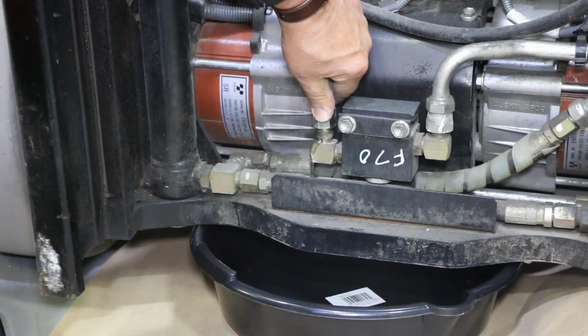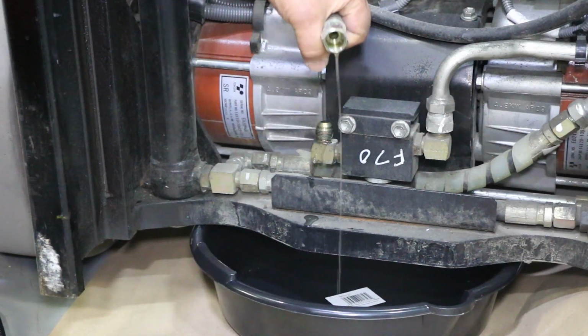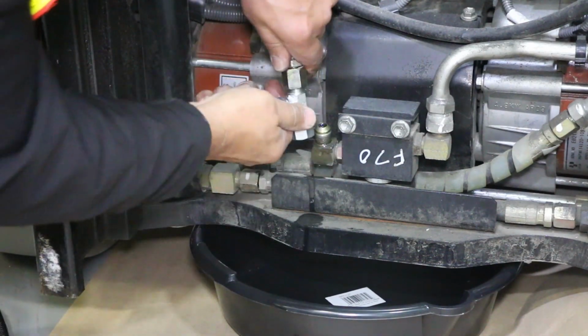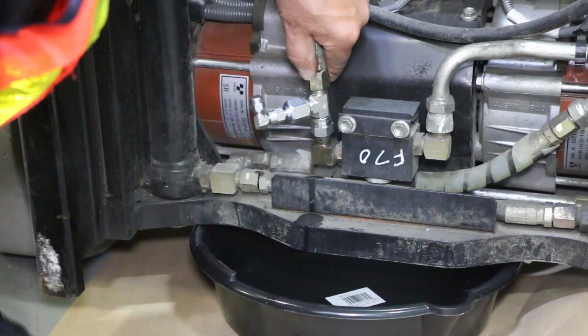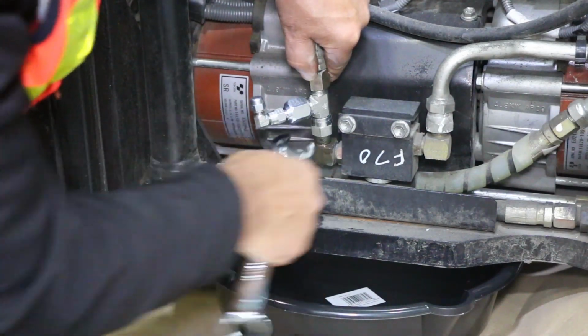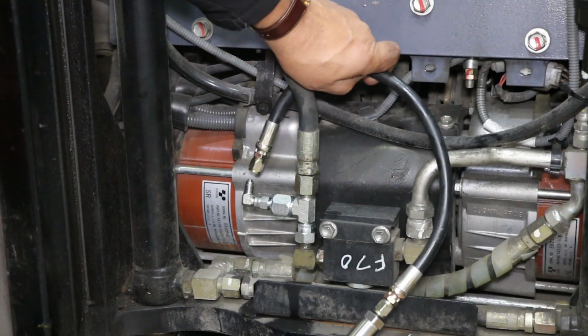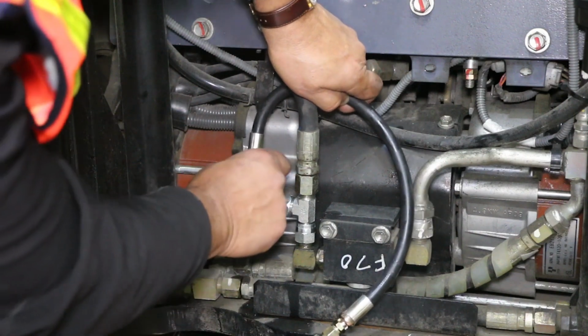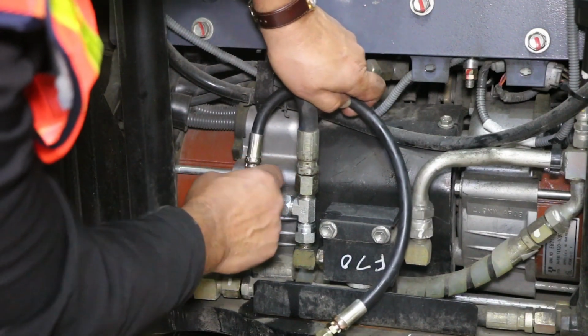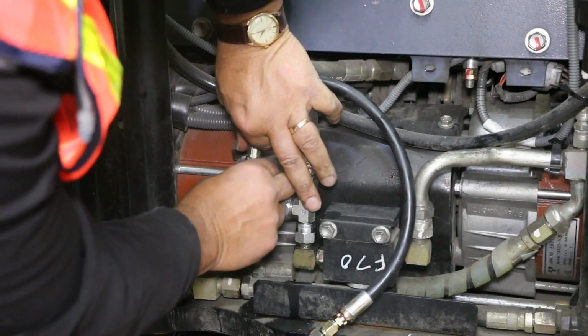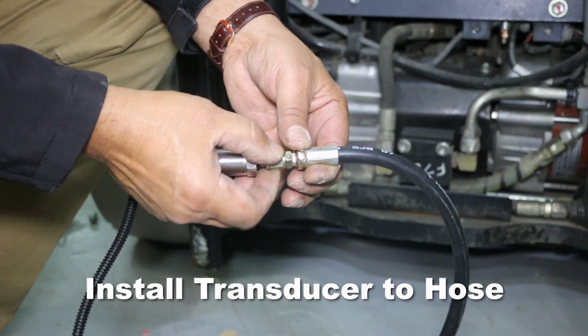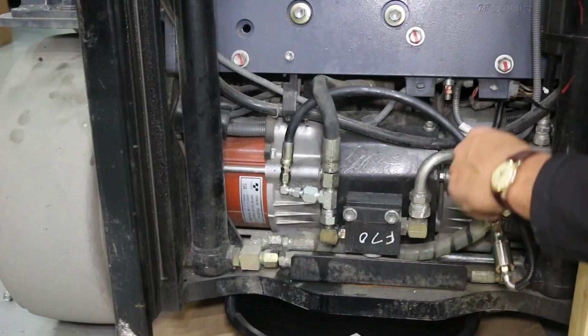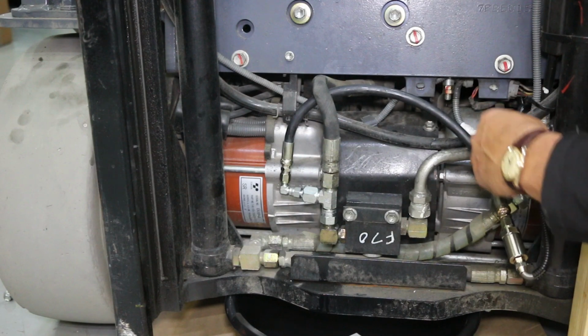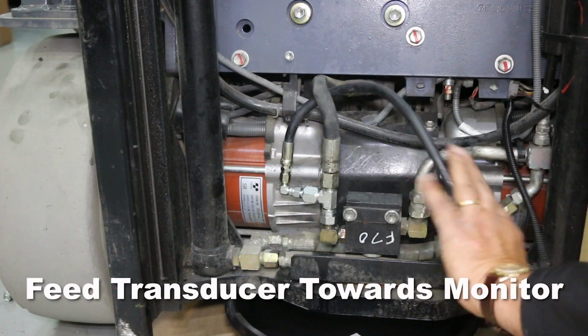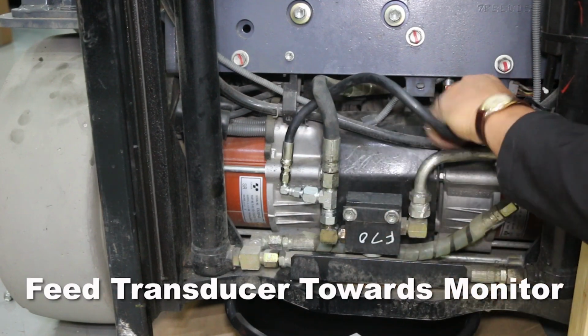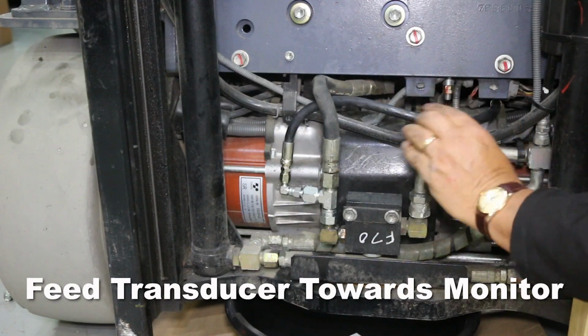Remove the hose that feeds the hydraulic cylinder. Then attach the hydraulic T-piece fitting to this line. Tighten both sides while ensuring the fitting and transducer will not obstruct the normal operation of the mast. Attach the hydraulic line to the transducer. At the other end of the transducer is an electrical wire that will connect to the weigh scale monitor.